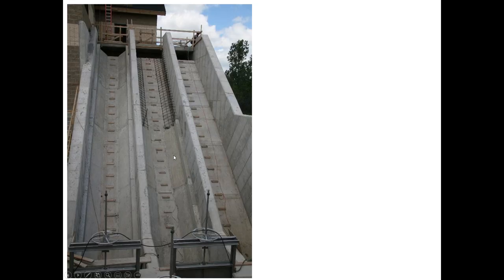I've got a picture in the next slide that shows that what you do is you set these large screws down into an angled trough, and then there would be a fixture around the side that limits leakage downward, and so as it screws, the water is lifted upward, and then each revolution brings a certain volume of water and dumps it into an upper basin here, and then the water begins to flow by gravity through the rest of the treatment plant.